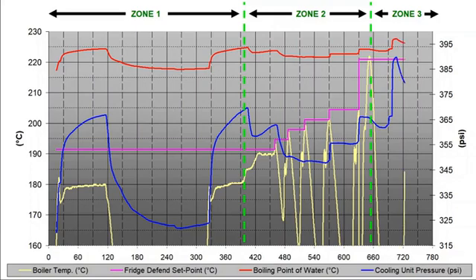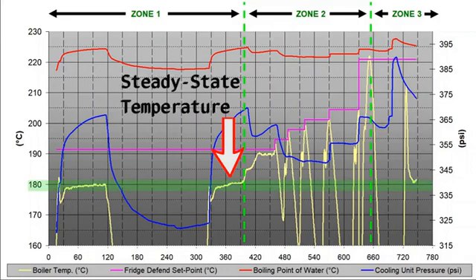Turning to the yellow boiler curve, the temperature rises until the pump fully resumes production of ammonia refrigerant. At this point, the boiler temperature drops to its normal steady state value. No damage has occurred to the cooling unit based on the fact that the water in the system never boiled, and boiler pump resumed normal operation which is evidenced by the steady state boiler temperature.